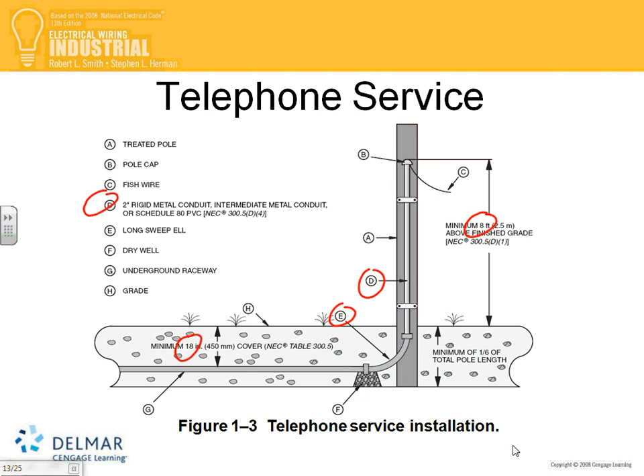If you're bringing power or the phone line from the utilities, you need D, rigid metal conduit, for physical protection. The same applies for power brought underground. You could continue with rigid, but if you're underground, your number one choice is PVC, to get full protection from corrosion and so forth.